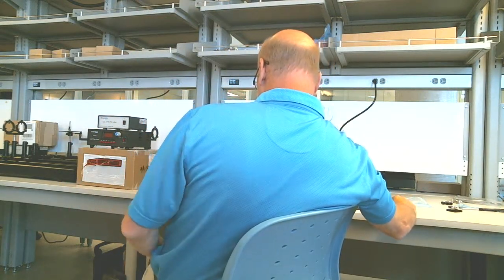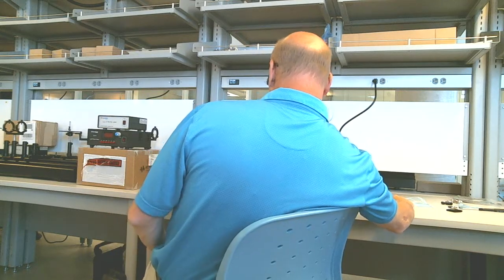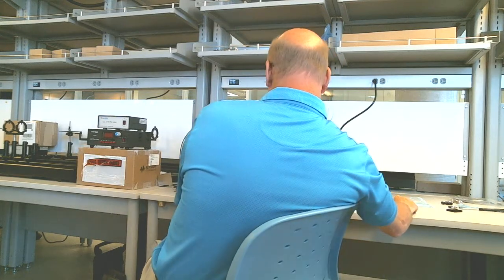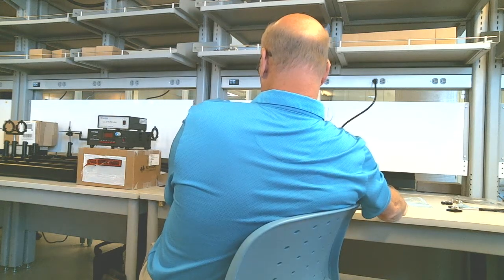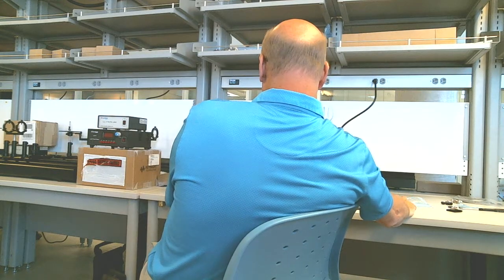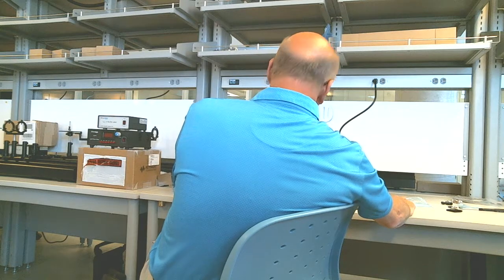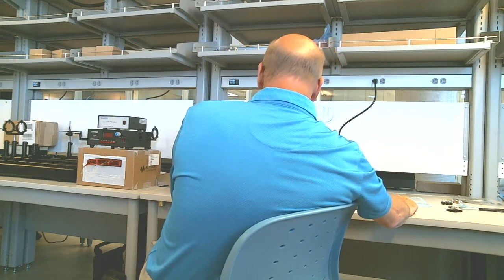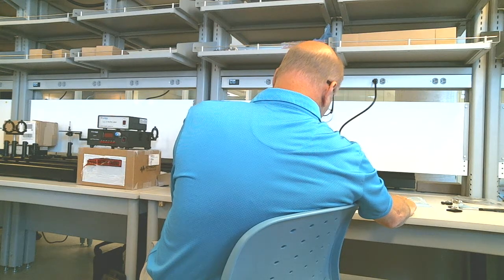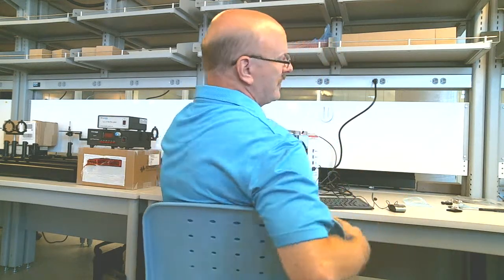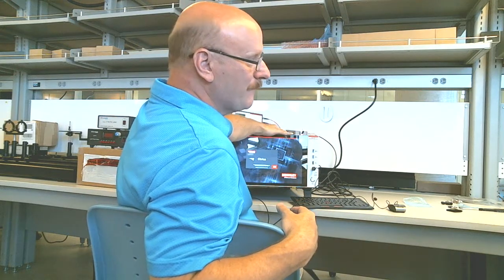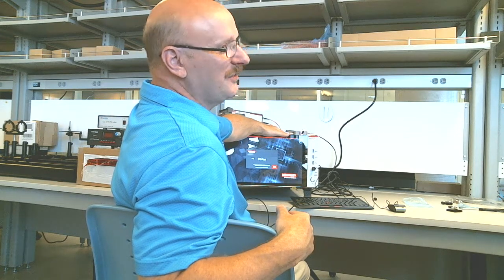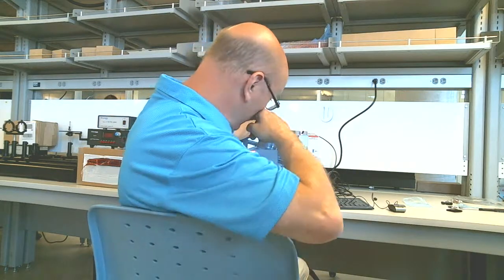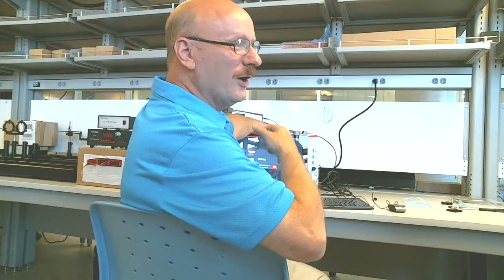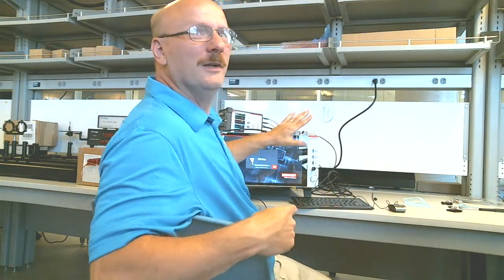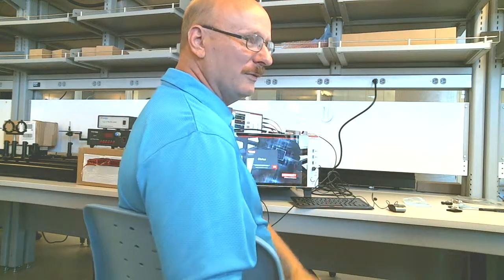Okay, this is not good, but I think I know what it is. Well, there's a trigger controller inside this box that triggers the SMUs. And sometimes during shipping they come unseated, the trigger controller. And if I run a UTM, it doesn't use the trigger controller. So if a UTM runs, that tells me that it's the trigger controller. So I can try running a UTM, and we can see if that runs. If that runs, then we can open it up and see if we can reseat that card. That's likely.